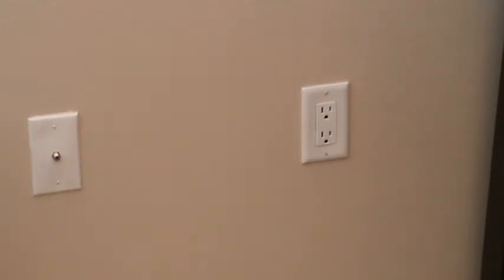12-2 with ground is to be used on a 20-amp circuit. 14-2 with ground is a Romex cable with a black wire, a white wire, and a bare copper wire in it — that's what it's called. It's a Romex cable and there's a sheathing around it with those three wires inside. 12-2 with ground is the same thing except the wire size is a little bit bigger. 14-2 with ground is for a 15-amp circuit.